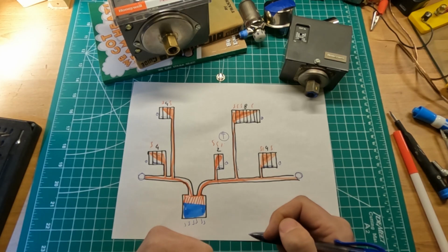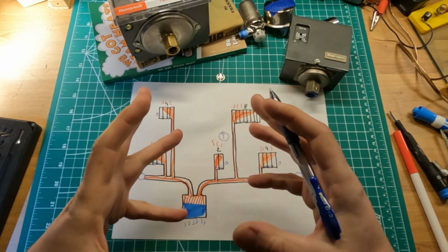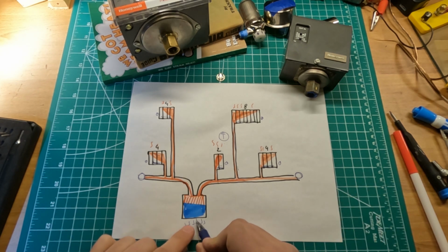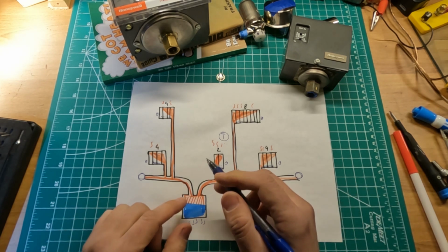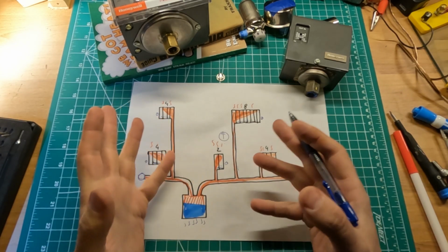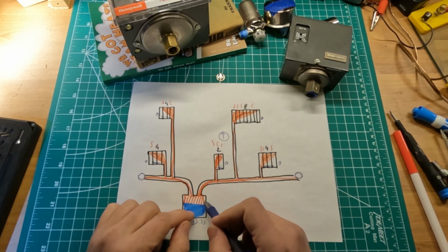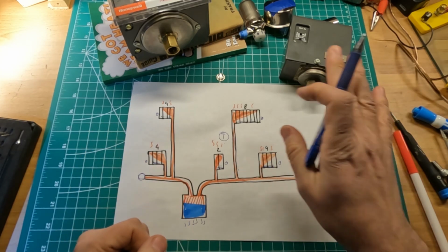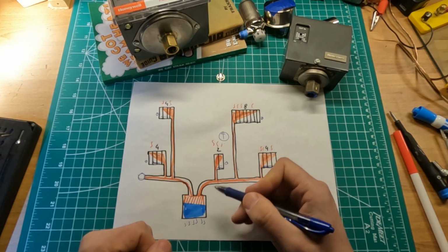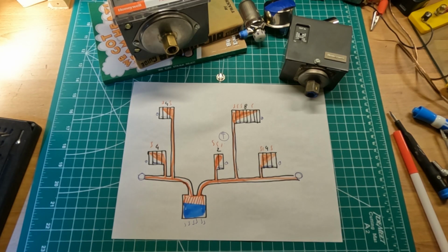And then what ends up happening is this is basically wasted energy, because you're paying for the energy to heat up this boiler, and at the same time that pressure indicates that the steam has nowhere else to go from the inside of the boiler. And so for that, we have devices like those Pressuretrols that are meant to shut down the boiler when it reaches a certain steam pressure.